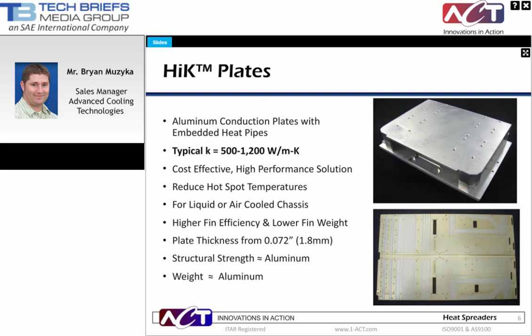High-K plates are plates with embedded heat pipes. Heat pipes are pressed into grooves or drilled holes and soldered or epoxied into place. High-K plates offer similar strength and weight as aluminum with much higher thermal conductivities. They can be manufactured as thin as 0.072 inches, and high-K plates are often used to reduce hot spot temperatures or increase fin efficiencies for air-cooled heat sinks. The thermal conductivity range is from 500 to 1200 watts per meter K. These values come from real-world applications, where we adjusted the bulk thermal conductivity of the plate in models until the hotspots matched tested results. The range is mainly dependent on geometries, as large form factors can achieve higher effective conductivities, since the delta T across the heat pipe is not a function of length.